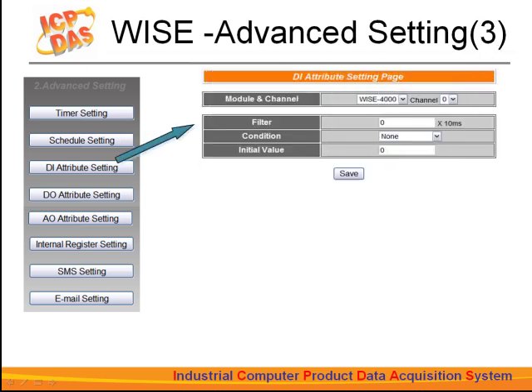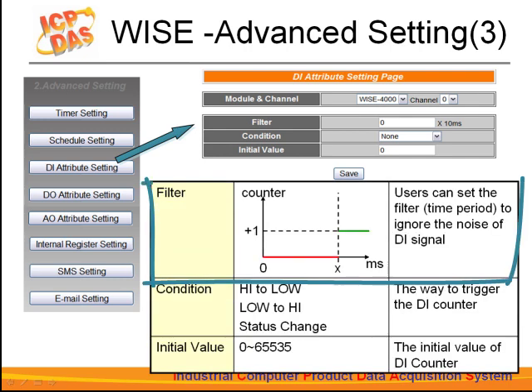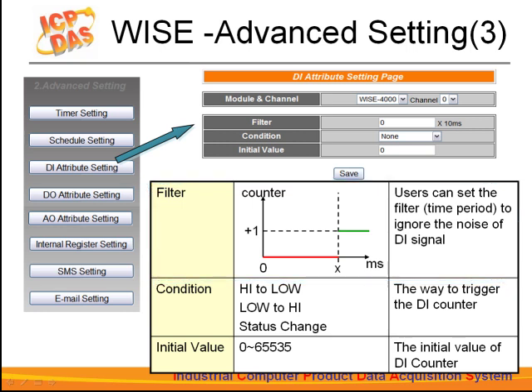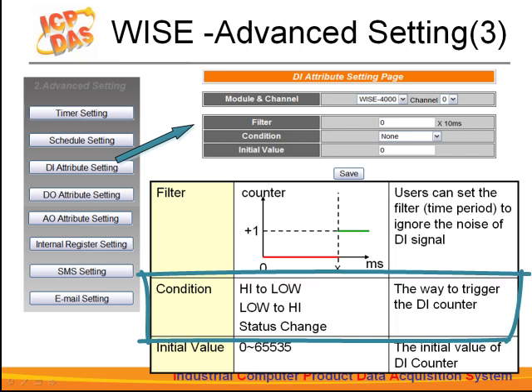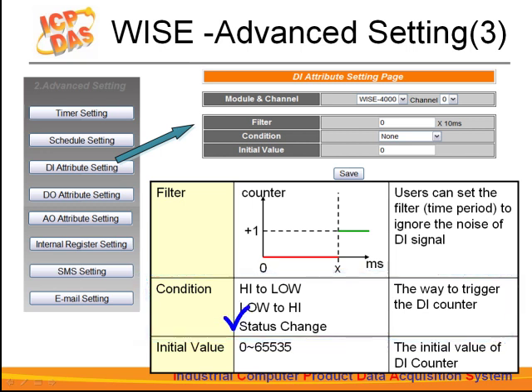Now we come to the digital input attribute setting. Digital input channels are used as counters. DI signals may face interference, so you can set a mask in the filter field to rule out interference. The time interval for the filter is the minimum duration a signal has to sustain to make a change to the counter. In the condition field, please set the trigger criteria for the counter. There are three options: high to low, low to high, and status change.